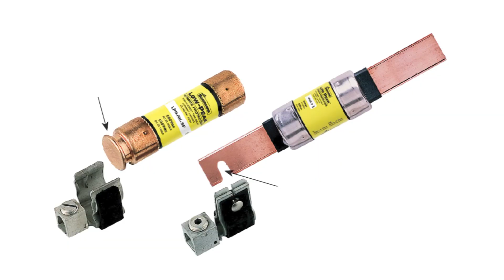In addition, current limitation helps achieve high equipment short-circuit current ratings by drastically reducing peak let-through current and protecting downstream low-rated devices. And finally, no damage Type 2 protection can be achieved with properly sized current limiting fuses, reducing downtime and improving overall system protection. The physical rejection feature of current limiting fuses helps provide a safe and reliable system by ensuring the same fuse class with the same voltage and interrupting rating is installed. This reduces the risk that the wrong fuse type with different performance characteristics and lower interrupting ratings could be installed and compromise the protection level.